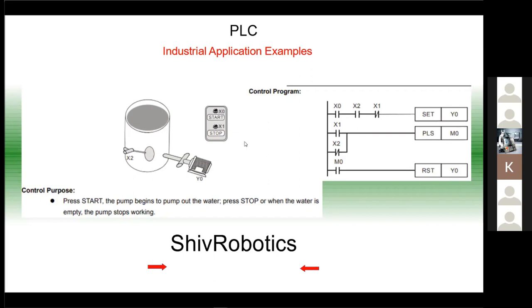So what do we have in our sequence? We have another logic, right? Along with the manual on-off button, we need an automatic way of switching off the motor if the tank is empty. So where do we incorporate this? This sensor is connected in parallel to the stop switch, but the status is inverted here. So this is the interesting part. You have to invert this and connect it in parallel to X1.